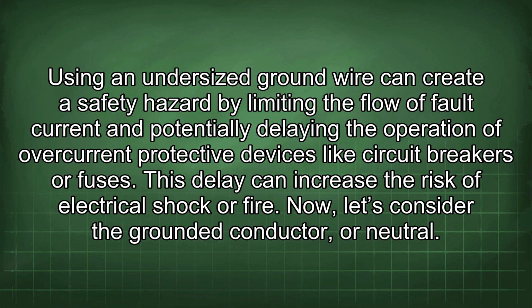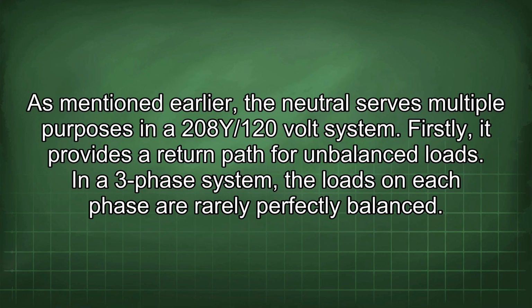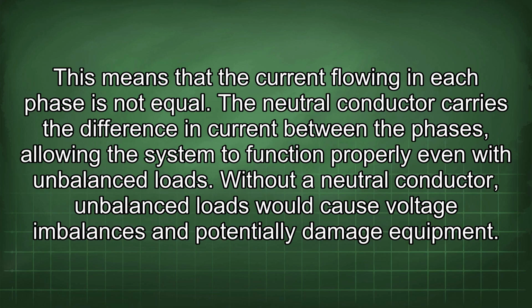Now let's consider the grounded conductor, or neutral. As mentioned earlier, the neutral serves multiple purposes in a 208Y/120-volt system. Firstly, it provides a return path for unbalanced loads. In a three-phase system, the loads on each phase are rarely perfectly balanced. This means that the current flowing in each phase is not equal. The neutral conductor carries the difference in current between the phases, allowing the system to function properly even with unbalanced loads. Without a neutral conductor, unbalanced loads would cause voltage imbalances and potentially damage equipment.